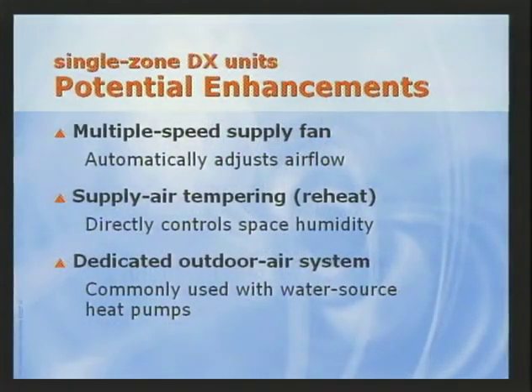We'll discuss two methods commonly used to improve the part load dehumidification performance of a single zone DX unit. The first is a multiple speed supply fan, and the second is direct control of space humidity by overcooling and reheating. In addition, a dedicated outdoor air system is sometimes used with certain types of single zone DX equipment. For schools, the most common example is probably a system that uses water source heat pumps.